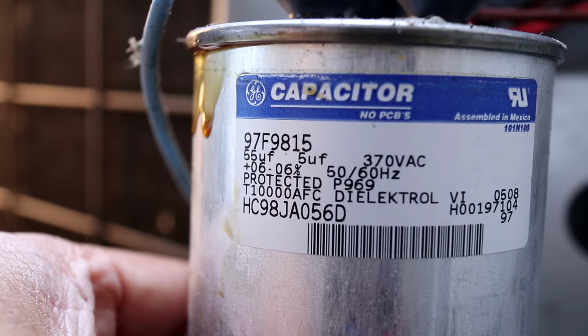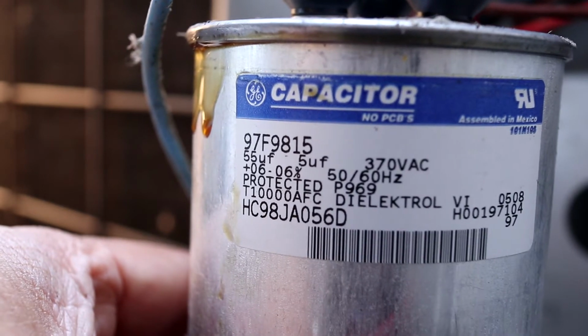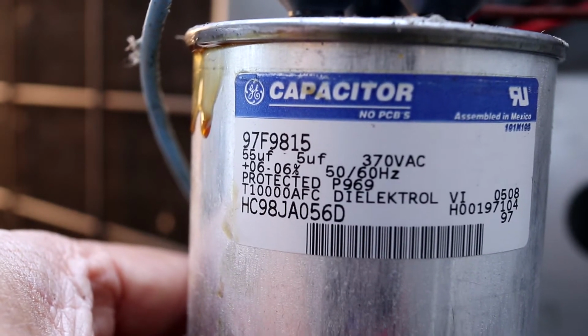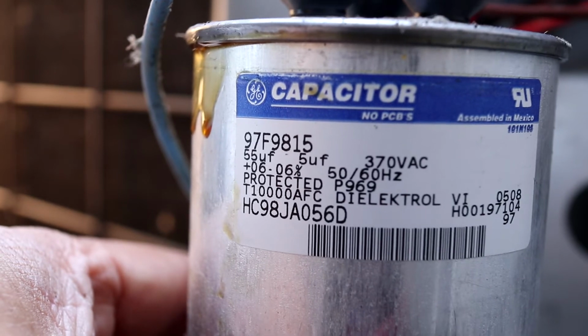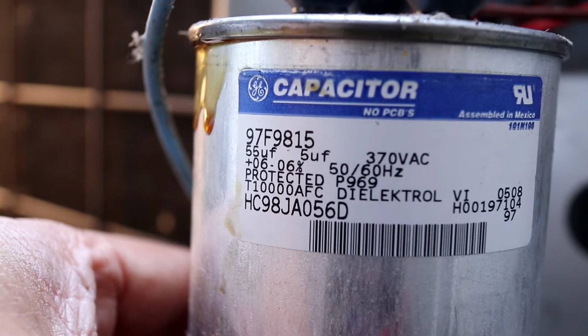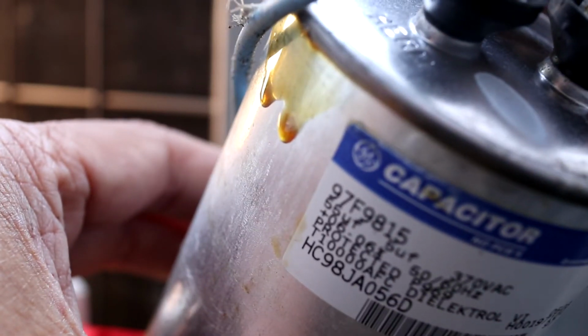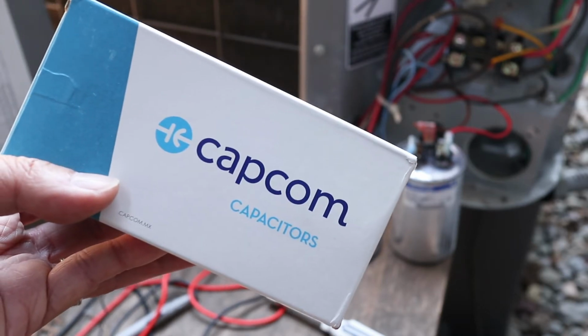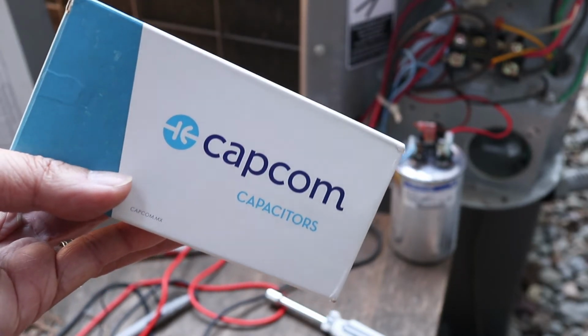When shopping for a replacement capacitor, it's important to get a new one with the same specifications. My old one is 55/5 microfarads and 370 volts. At this point, I'm sure this capacitor is bad because I can see it's leaking fluid and it's bulged up on top.